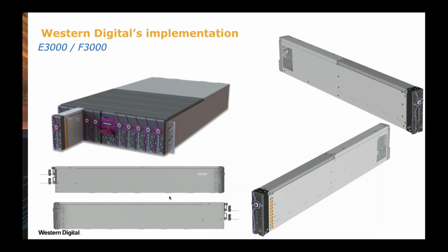I think it's fairly important to understand the power and thermal envelope. I know that you mentioned the chassis, Mark, and the chassis actually has the airflow in it. However, if someone wanted to build one of these sleds, they need to know what the max power envelope is. The connector will define the power envelope, and obviously your pinout will tell you your interface to it. But if the airflow is not sufficient, let's say you could cool 150 watts per sled, and someone's not aware of what the cooling capabilities are, they couldn't even begin to start a design.